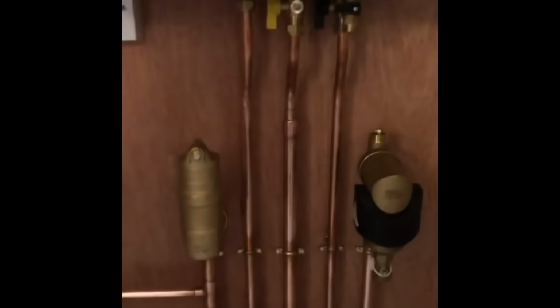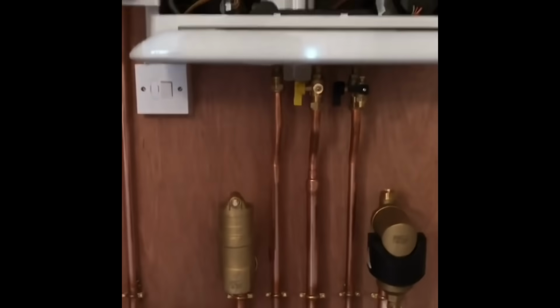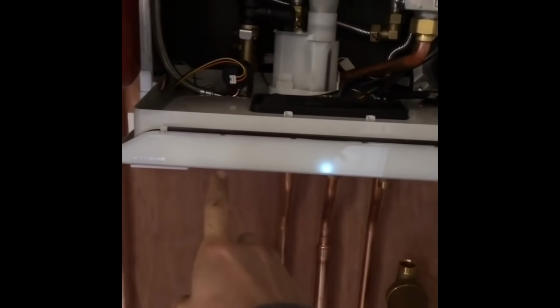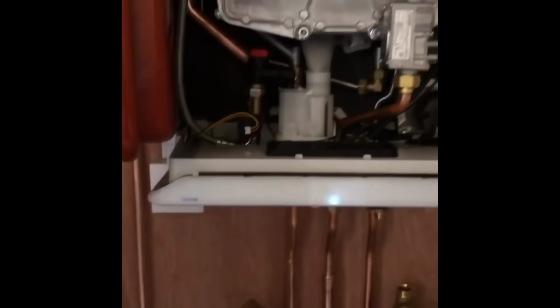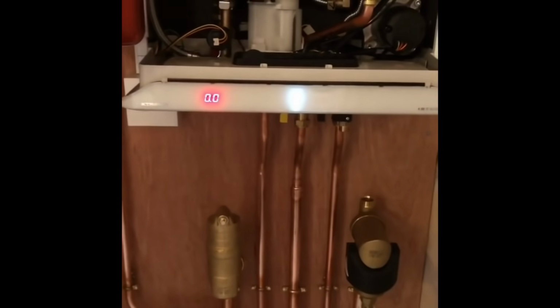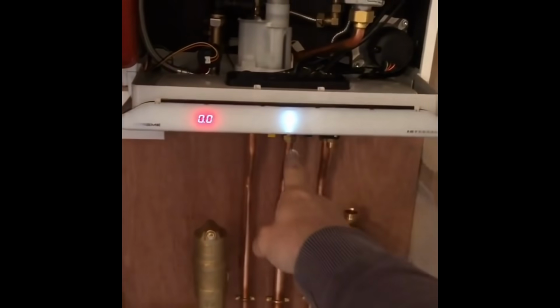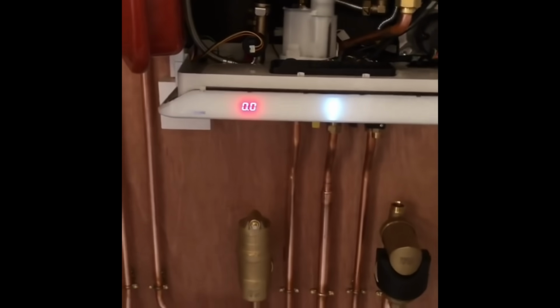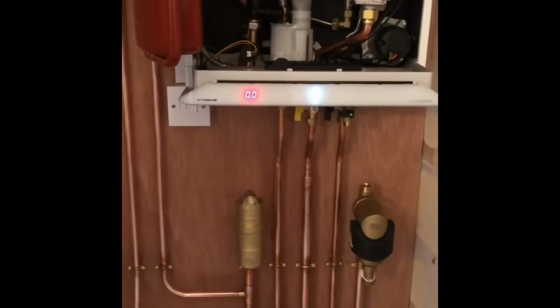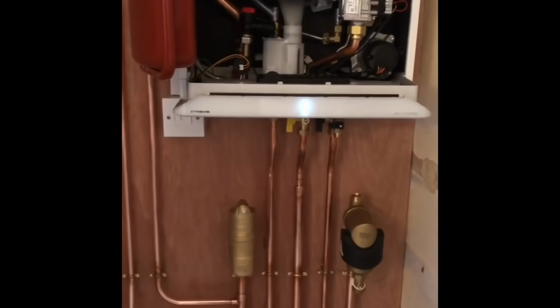Feature was really cool. So you can see here I've not yet piped up the central heating flow or return on the system, and there's no pressure in the boiler. Now on a normal combi boiler you won't get any hot water at this stage, but because of the unique design of the Intergas heat exchanger, at this stage in the game we've got hot water. The way it works is we've got separate waterways for the central heating and the hot water, and there's no plate heat exchanger or diverter valve.